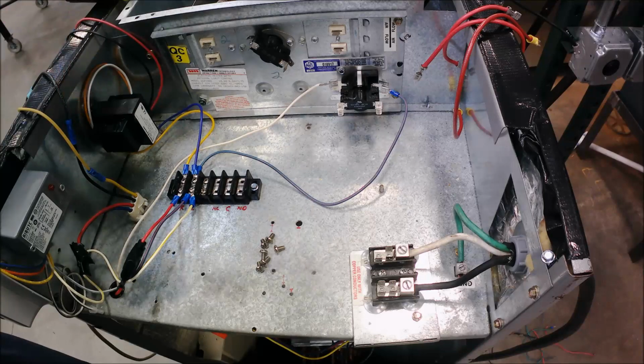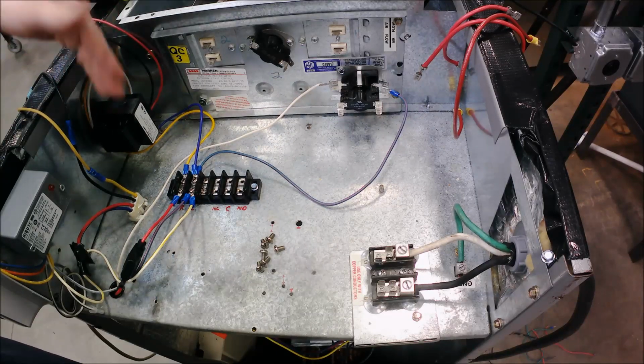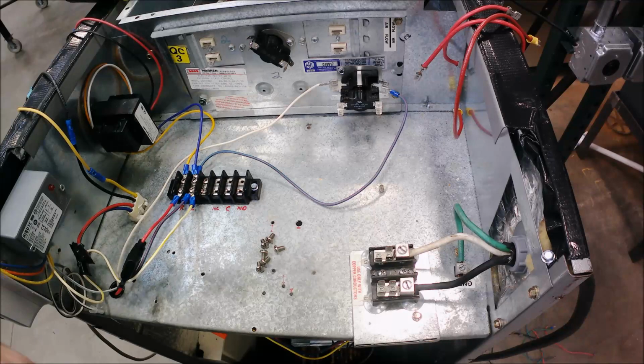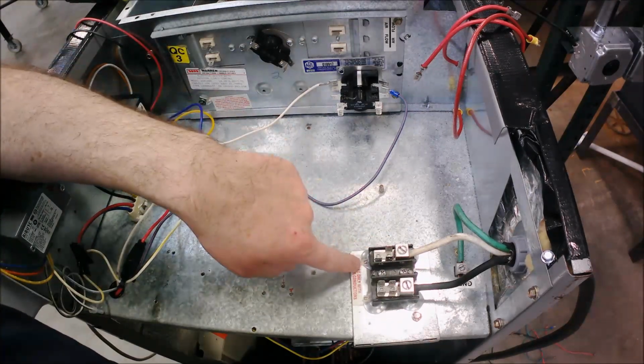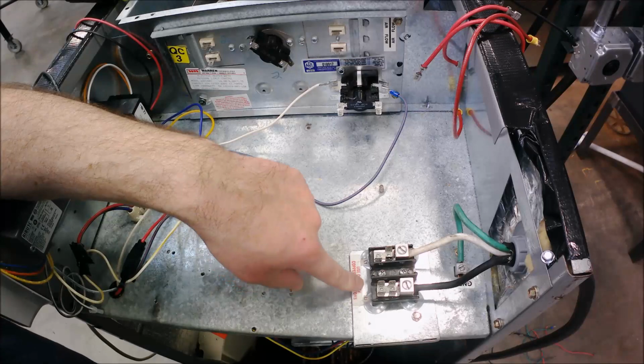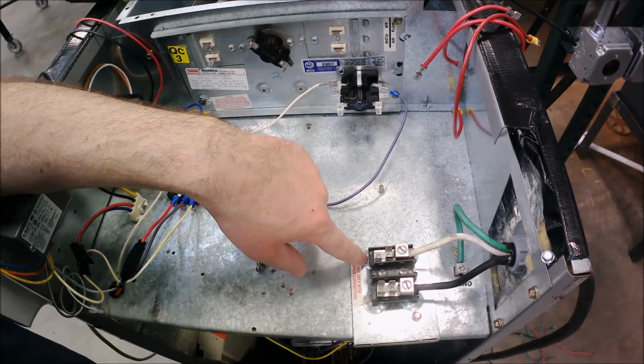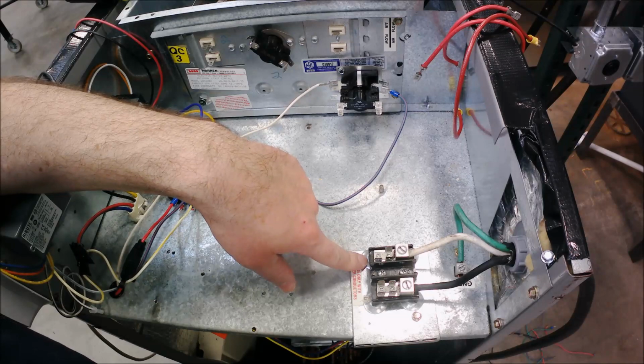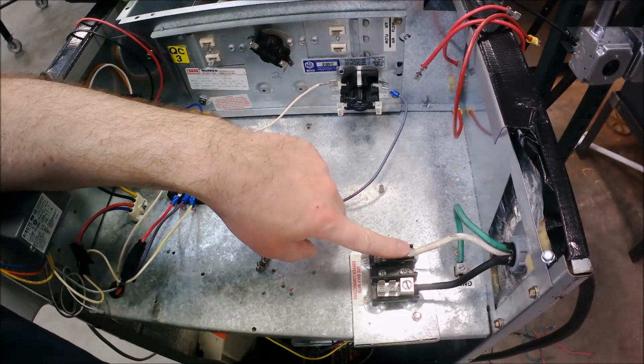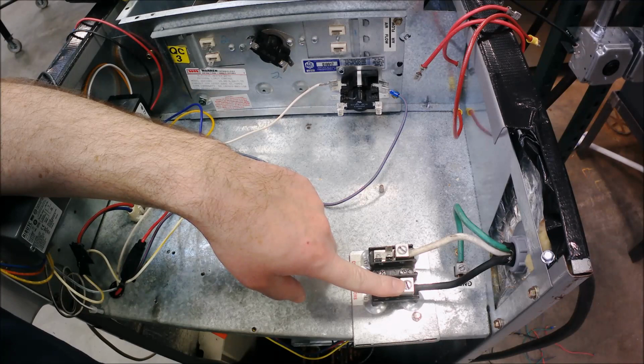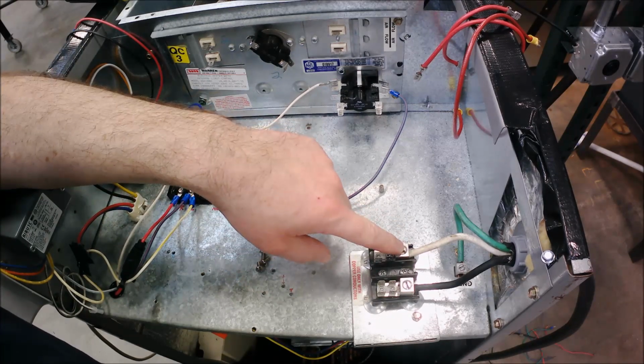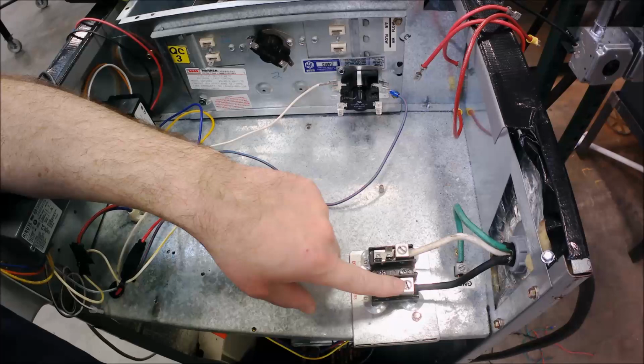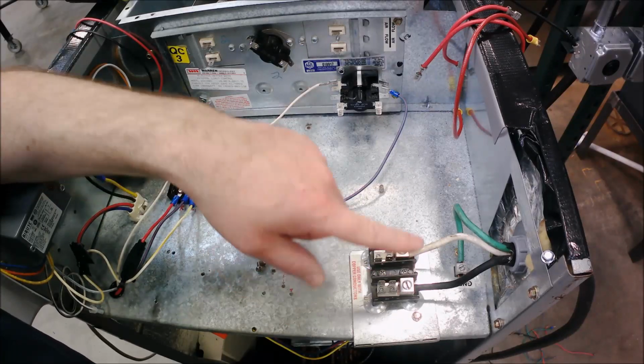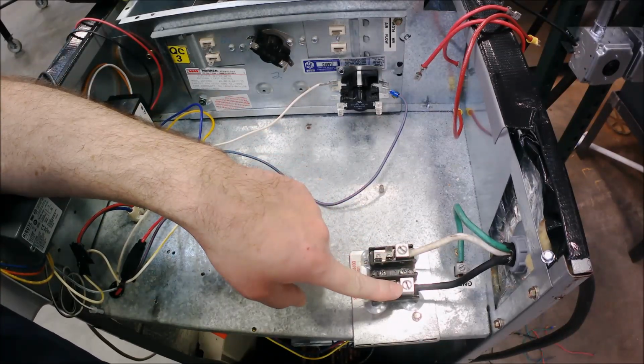So we've got to wire up the heat strip. We have to wire up the transformer because we have to have high voltage to get low voltage. We have to wire up the fan motor because our blower has to run anytime the heat strips run. When we're coming off the terminal block, they've already labeled these L1 and L2. To me, that doesn't matter. I remember that I have to start on one side and end on the other. You can start on the one on the upper section as you're looking at it, and as long as you end on this one, everything should be fine. Or vice versa. I can start on the bottom and end on the top.